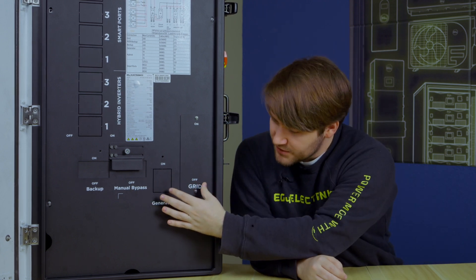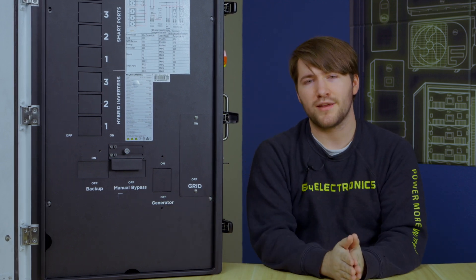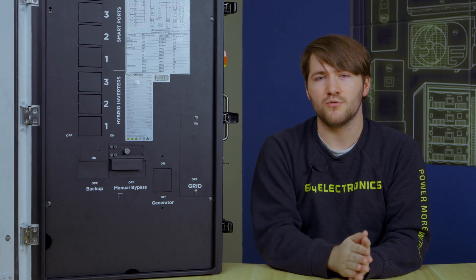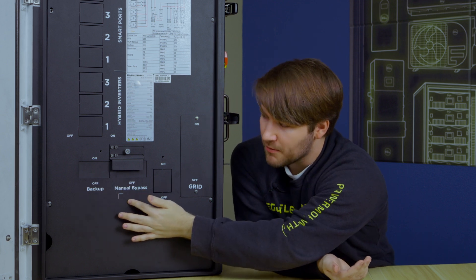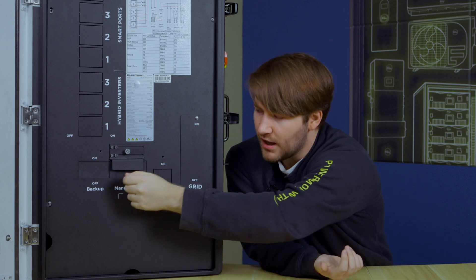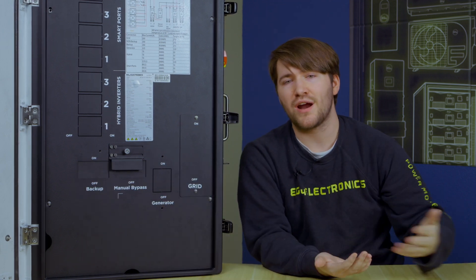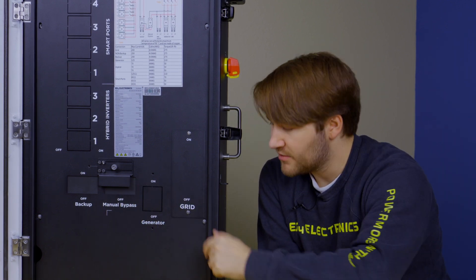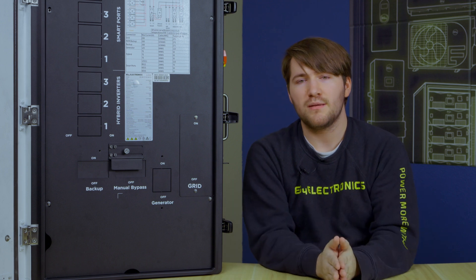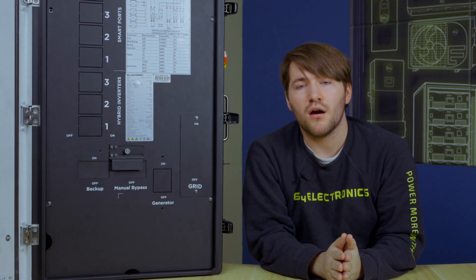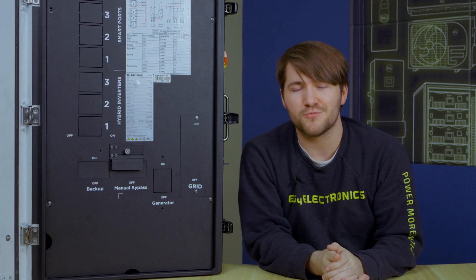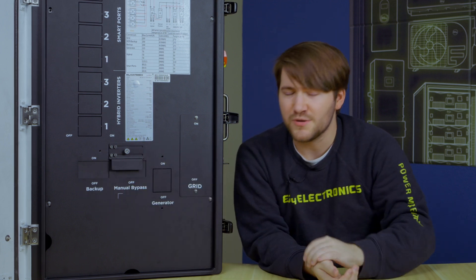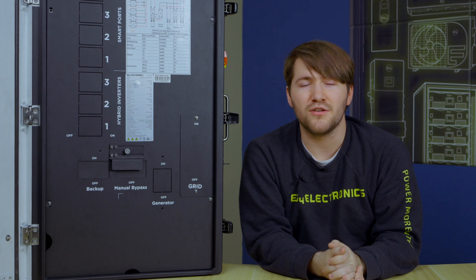And last but not least, we have the grid port here for a properly rated grid breaker up to a 200 amp service. Now there is a backup and a manual bypass port here. And what this will do is allow you to turn off your hybrid inverter output to your system and manually back up your system with the grid. And that will allow you to, say you want to do some maintenance on your hybrid inverters, but you don't want your family to be without power for the next two hours while you're wiring something in. All you do is simply switch over using the manual bypass and you're running on grid power until you say otherwise.